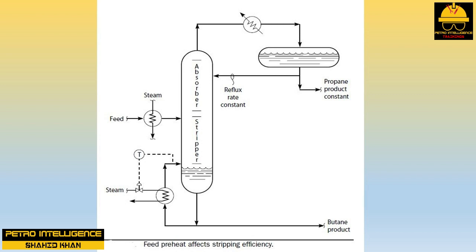How does this increase in feed preheat affect the flow of vapor through the trays and the fractionation efficiency? The bottom part of the tower below the feed inlet is called the stripping section; the upper part above the feed inlet is called the absorption section. Since both reflux flow and overhead product flow are constant, the weight flow of vapor leaving the top tray is also constant regardless of the feed preheater duty — this is approximately true for all the trays in the absorption section. For the bottom stripping section trays, a reduction in reboiler duty will directly reduce the vapor flow from the reboiler to the bottom tray.